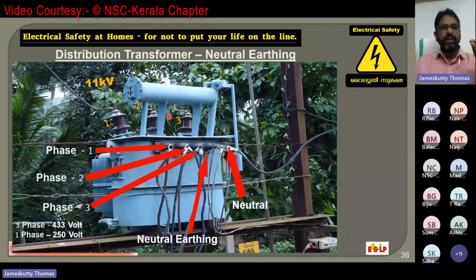At the primary of the transformer, 11 kV supply is given from the nearby substation. Usually such a transformer will be rated 11 kV/433 V. It means if you give 11 kV supply on the primary side, we will get 433 volts on the secondary side. Another important point is that the same phases R, Y and B will be there at the primary and secondary. At the secondary side, the voltage between 2 phases will be 433. Remember, in the secondary, only 3 phases or 3 wires are there. Let us see how the 4th wire, or the neutral, is created.